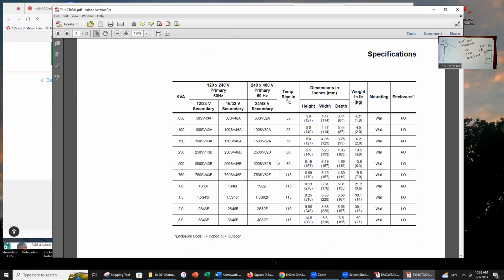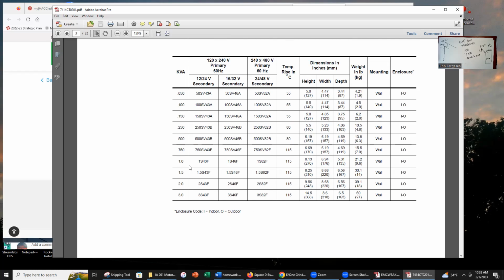And we also specify in this primary table, this is the primary table that's right at the beginning of this. It shows you the kVA on the left. It shows you the part number if I'm going to go 12 or 24 volt secondary. And here's the part number that I want, which is the part number for the 16 or 32 volt secondary. So that 1S46F part number will give me what I want in terms of a 32 volt secondary. So I've got my part number right there, straight from Schneider Electric's transformers.